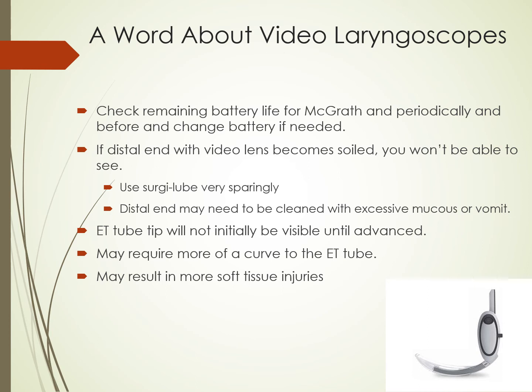So I mentioned earlier that many of the models will have a battery that's just replaceable, non-rechargeable. It's a good idea to check the remaining battery life for the McGrath scopes and other similar scopes periodically. So for instance, when I come into the unit, my mental checklist is I will just get the video laryngoscope and check to make sure that somebody didn't clean it and put it away but forget to turn it off. So you'll have a depleted battery, and you don't want to be at the head of the bed in an emergent intubation and you're screwing around with replacing the battery.